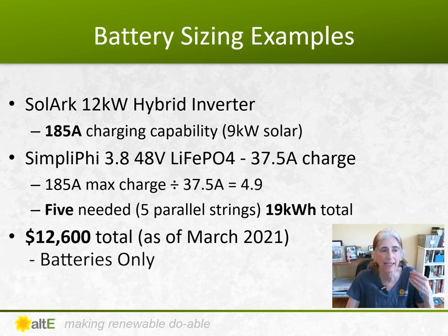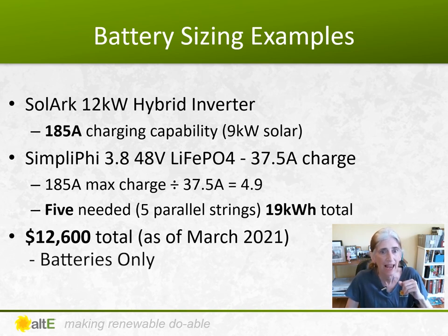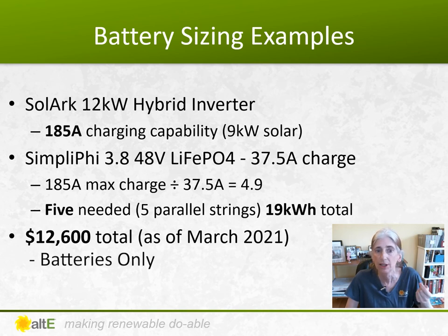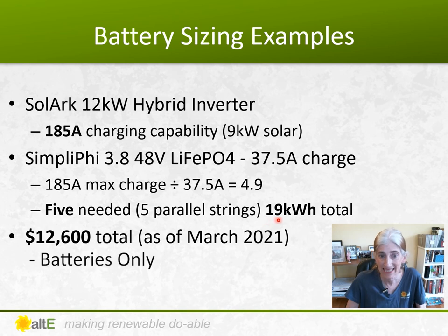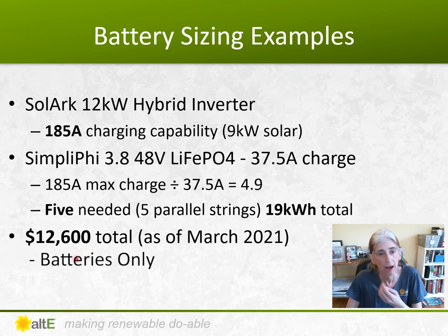The final example uses SimpliPhi batteries — those 3.8 kilowatt hour, 48-volt batteries with a maximum 37.5 amp charge rate. With 185 amps divided by 37.5, we need five parallel batteries. Since these are already 48-volt batteries, no series connections are needed — just five in parallel. That gives us 19 kilowatt hours total, at a cost of $12,600 as of March 2021.